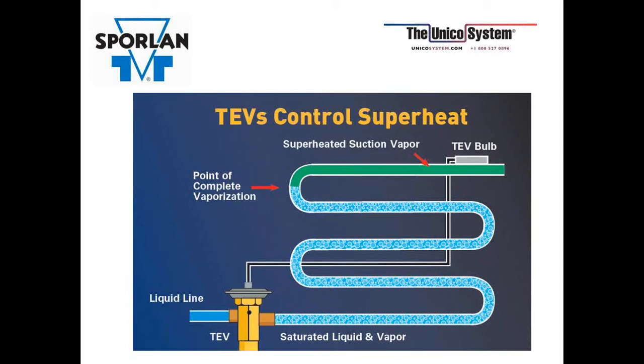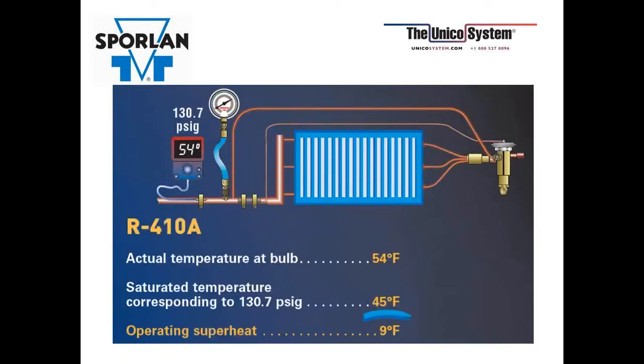Notice the point of complete vaporization. We typically want to have that somewhere at the last bend to the outlet of the evaporator. And it's that point of complete vaporization when the saturated liquid has become 100% vapor. And superheat is nothing more than the difference between the actual temperature and the saturated vapor temperature.